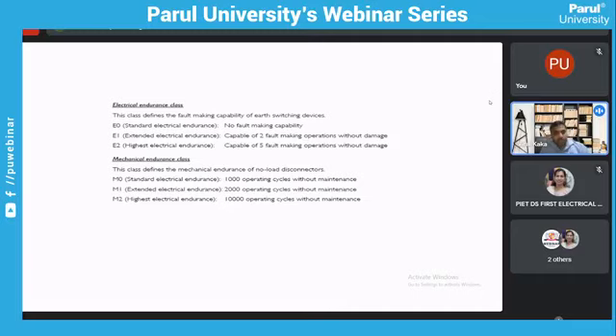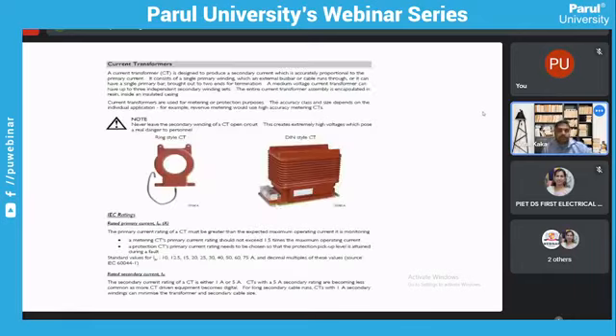M2 is something which you will see normally in all of the medium voltage primary switchgears. There are secondary switchgears with limitations, where they have tested the breakers with fewer operating cycles, and that is M1. So we will see M1 as a mechanical endurance class only, from what I remember off the top of my head, on secondary switchgears, but not on the primary.